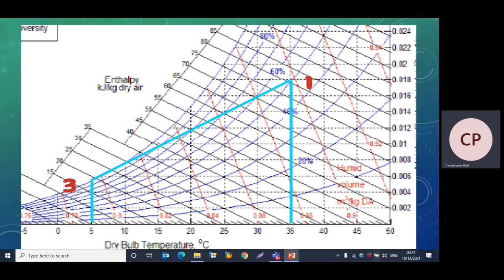To plot point 3, we select the apparatus dew point temperature of 5°C on the dry bulb temperature axis. When the apparatus dew point is given, we take relative humidity equal to 100%. So the intersection of the 5°C line with the 100% relative humidity line gives us point 3. Remember: ADP is always plotted at 100% relative humidity.